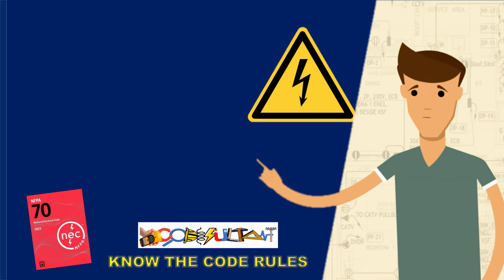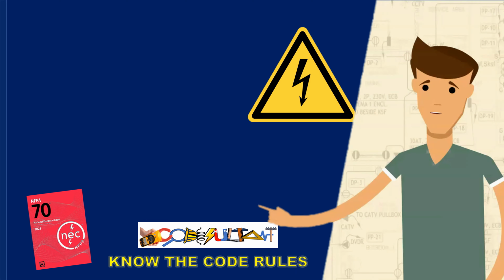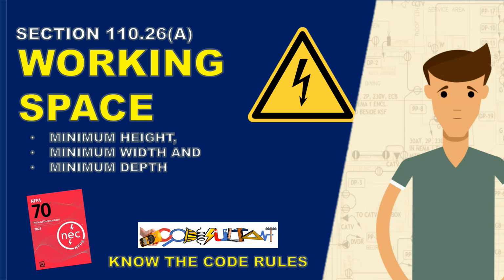We will be discussing an important aspect of electrical safety: the working space required for equipment that may require examination, adjustment, servicing, or maintenance while energized. Ensuring an ample working space is of utmost importance to guarantee the safety and protection of the individuals involved in these tasks. Our focus will be on understanding the minimum clear distances mandated for working spaces, which encompass the minimum height, width, and depth required for a safe working environment stipulated in Section 110.26(A). Without any further delay, let us allocate enough space for this enlightening exchange of knowledge.